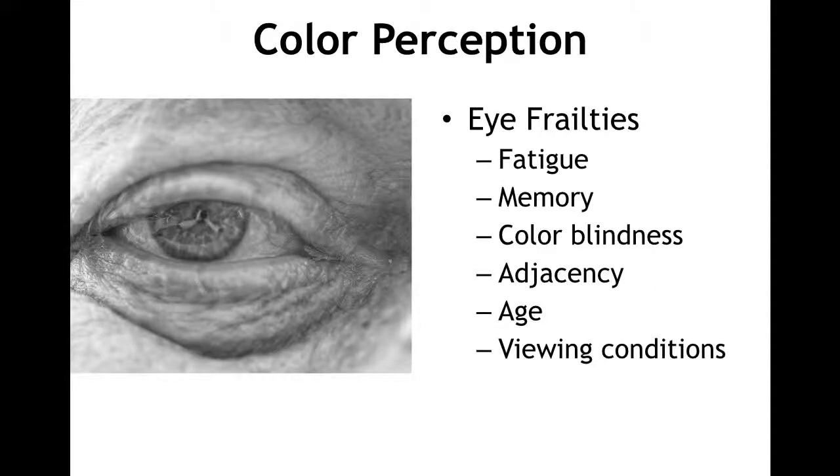It's also why our instruments are manufactured in what we call a 45/0 geometry. It simulates the eye. That light that comes in at 0 degrees is the light we see color with most accurately.